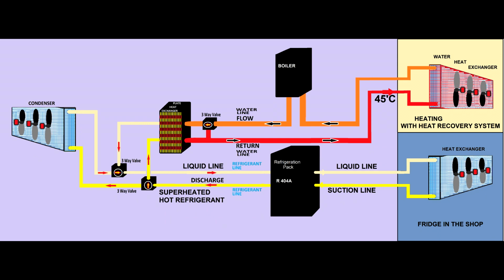So what you have to understand from this picture is that the refrigerant is diverted, so it's not going 100% through the condenser. Part of it goes through the plate heat exchanger, and it is heating the water which is circulated through the downflow heaters, and the downflow heaters have fans, and they transfer that heat back into the store. But to have this possibility, we need another source of heat. We have to heat the store. There won't be anything to recover if you do not have a heat source, and that's why I put in a boiler. And please don't leave, because I'm going to explain in more detail how this system works.